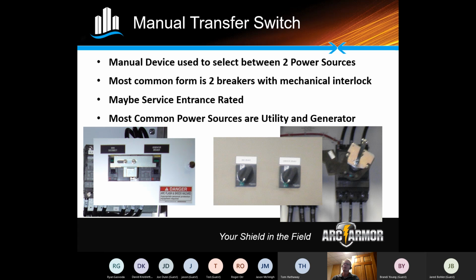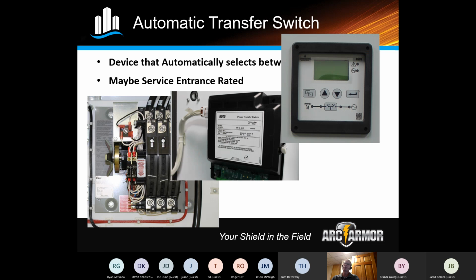And this is what it would kind of look like through the inner door. The other type is an automatic transfer switch. Same thing as the manual transfer switch, switches between two different power sources. The biggest difference between an automatic transfer switch and a manual is the automatic transfer switch has tie-ins to also automatically start the generator. So there's always a generator normally on site. They're interfaced directly to the generator control panel.